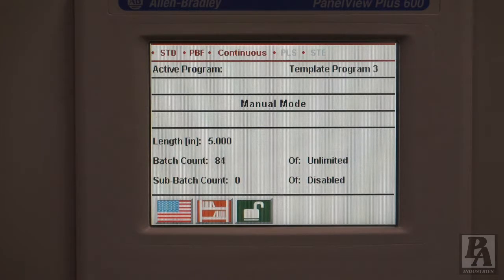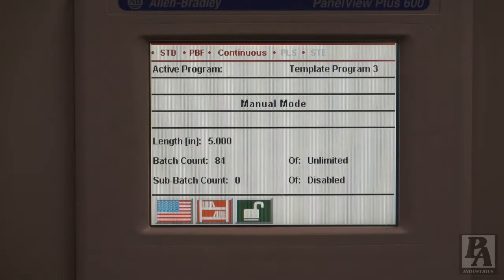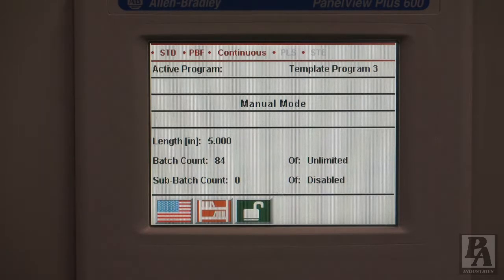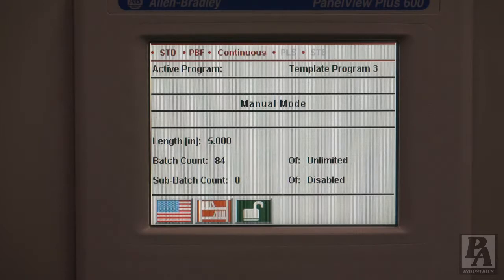Startup mode can also be displayed on this line, and if that is the case, the feeder has not completed booting up, making it impossible to jog material or switch into any other mode. After booting up and pressing the power button, the feeder should automatically enter manual mode. If the feeder is stuck in startup mode, check to ensure that there are no loose connections within the control box.